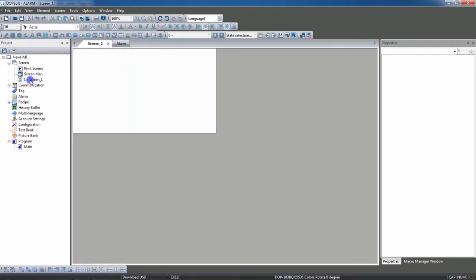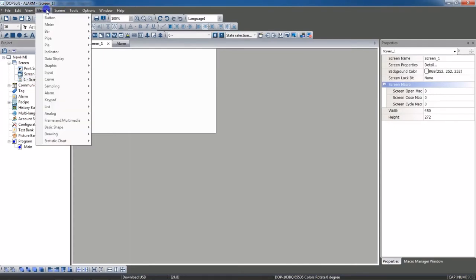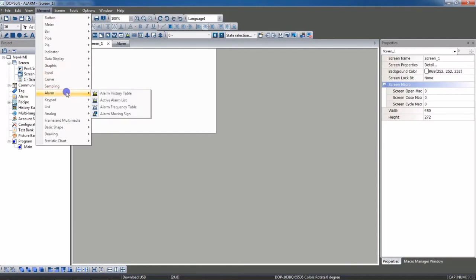Now go to the screen. From the Elements panel in the Alarm section you can take an alarm history table or an active alarm list. The active alarm list will show only current active alarms, while the history table shows the history of alarms. It depends on how you want to display them — I will select the active alarm list.